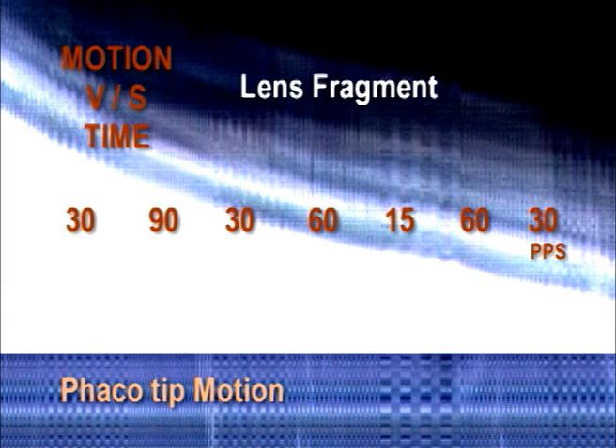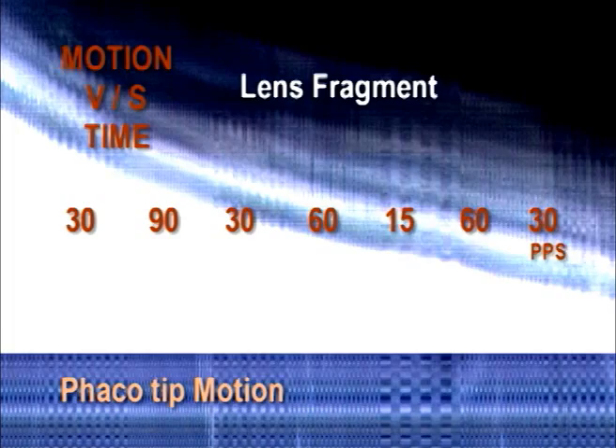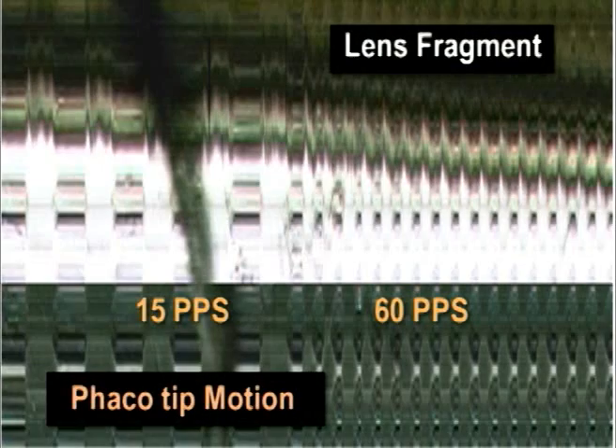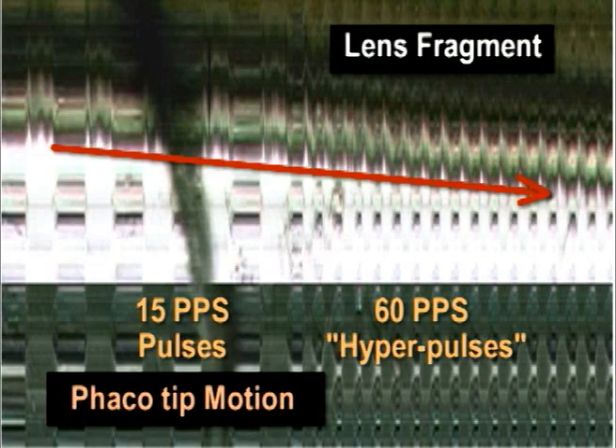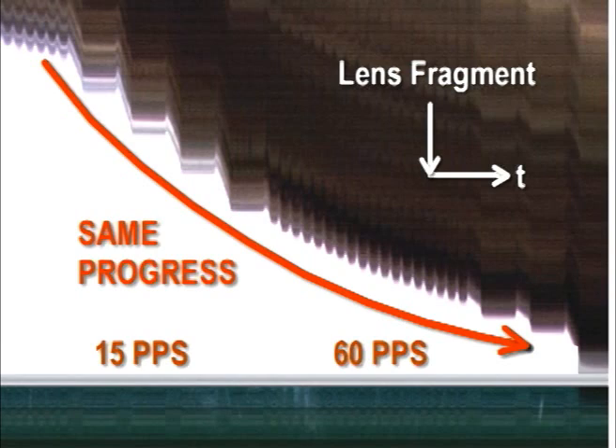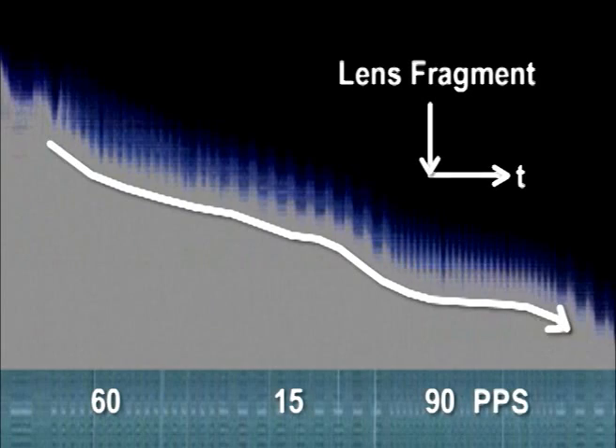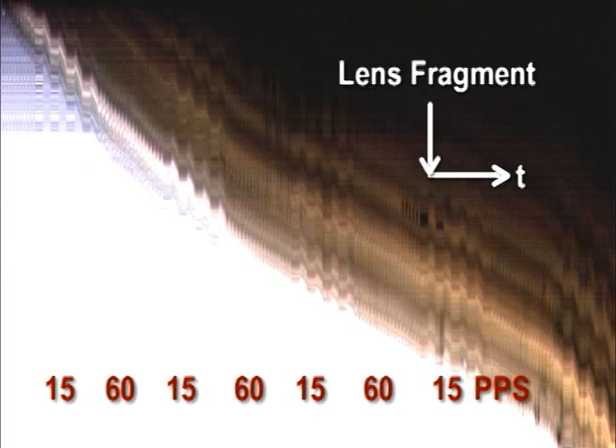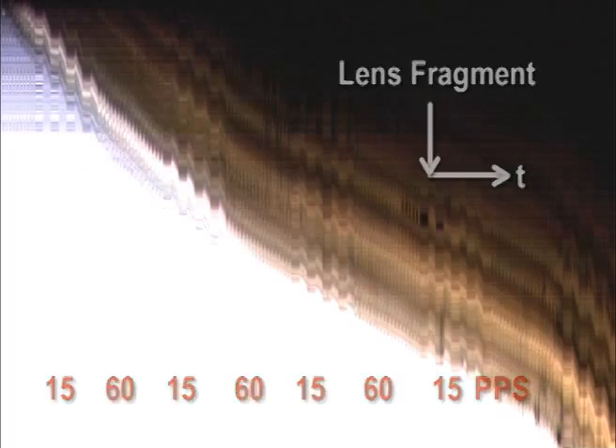High-speed video recordings have shown that the overall slope of fragment advance into the phaco tip is the same for pulses and for hyperpulses. Several experimental runs under controlled conditions failed to show any difference using several power and vacuum settings.